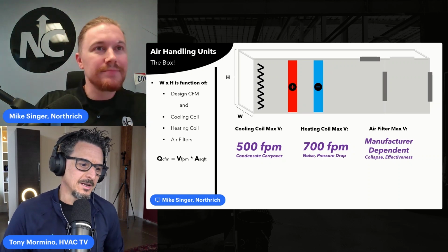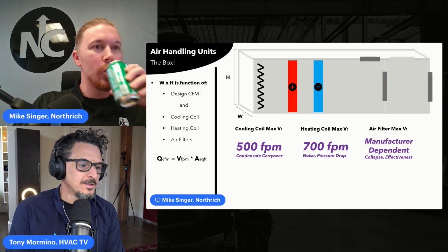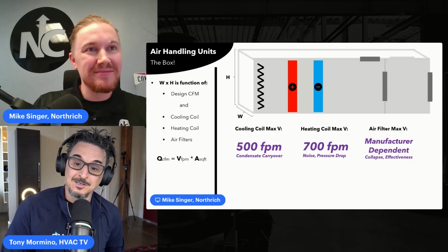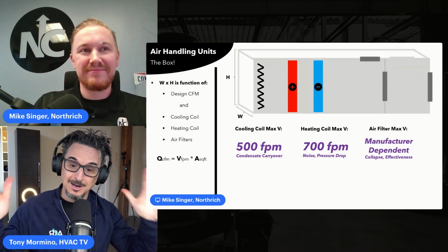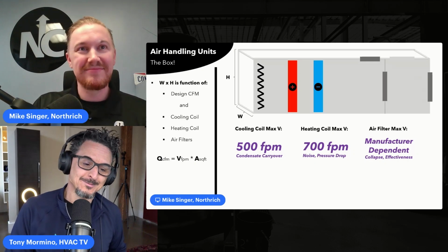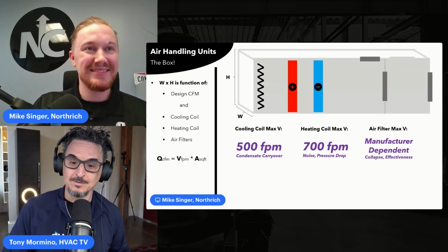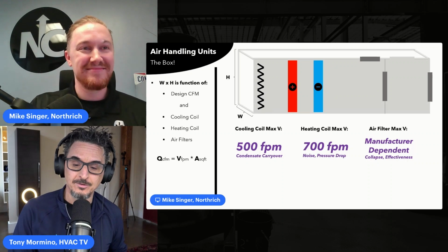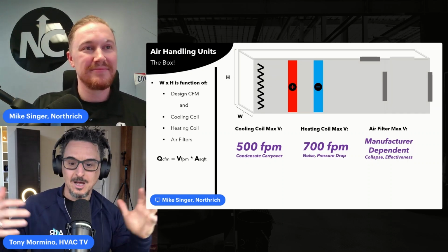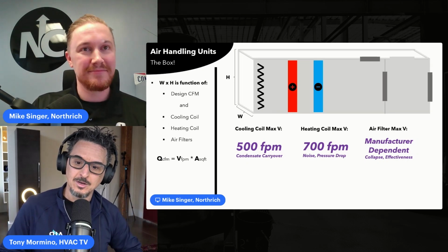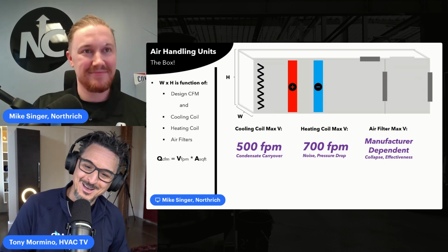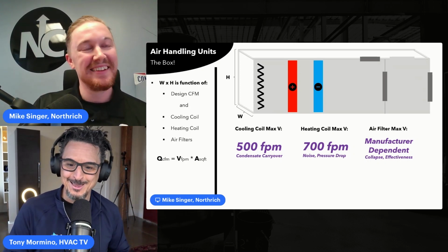That's good stuff. We did get a comment: we should not do that anymore, we need low pressure drop design. Well, yeah, but we don't make that decision typically. What usually happens is we send our ideal selection to an engineer and he sends it on and the architect's like, we don't have that much room, you've got to make it smaller. And it gets shrunk down based on those parameters, not on the science behind it, because obviously the lower the pressure drop, the lower the energy consumption, the lower the acoustics. There's so many benefits to it. You get more room for maintenance, but unfortunately we're not the sole decider on that problem.